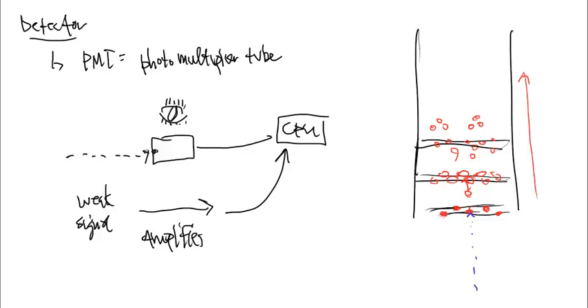So that's the photomultiplier tube, which is what we call the detector, and that is how it does its job. It's basically a little bitty light bulb, that's all that it is, or it looks like one at least. And this little bitty sensor is able to amplify the signal in such a way that it can create a large disturbance for the software to pick up. So PMT tube, or PM tube, photomultiplier tube, and that is what we call the detector of the instrument.